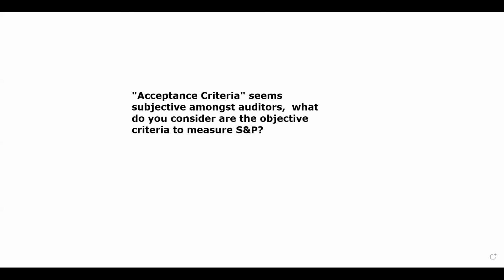Acceptance criteria seems subjective amongst auditors. What do you consider to be the objective criteria to measure safety and performance? So really the acceptance criteria are pretty well defined. Your acceptance criteria is going to be the range of data that you've identified. So again, taking the glucose testing example, if you have a particular test that's able to identify high glucose levels with the sensitivity of 89%, and then you have a newer test that's now one of your direct competitors, and that bumps that range up into the 90s. You would want to make sure that you are collecting your acceptance criteria from your competitors, not necessarily all of the alternatives.